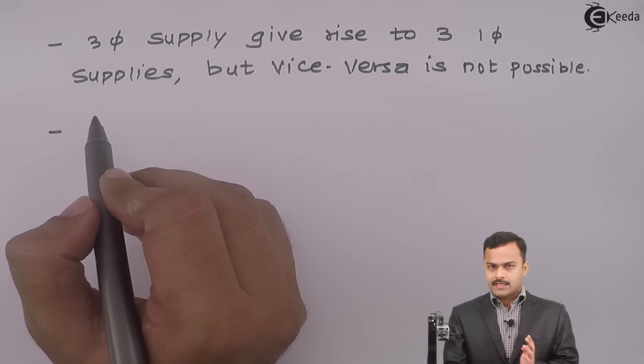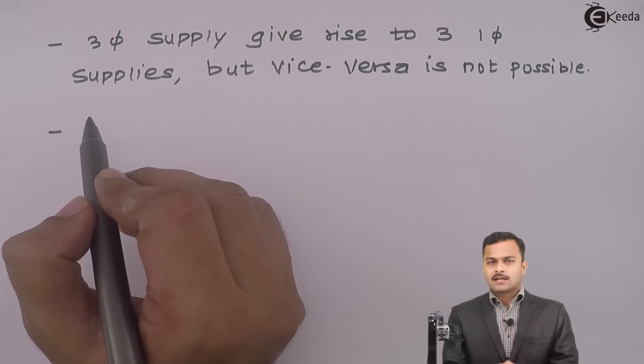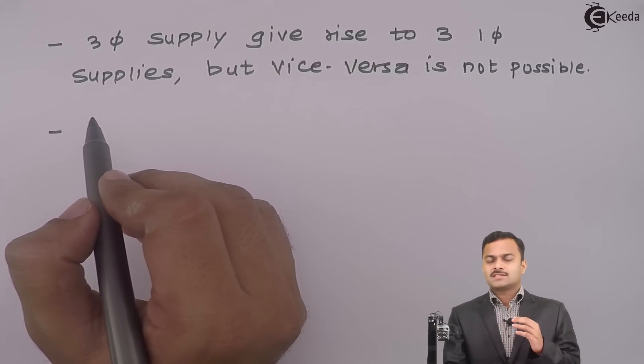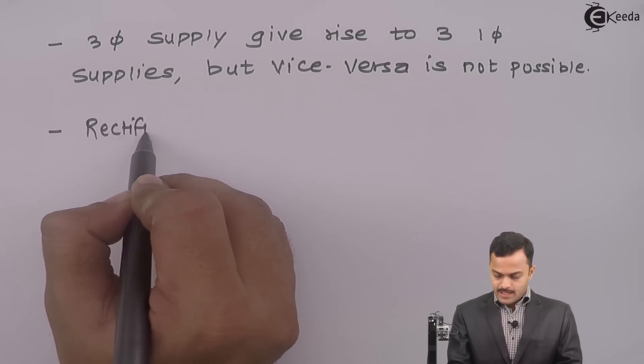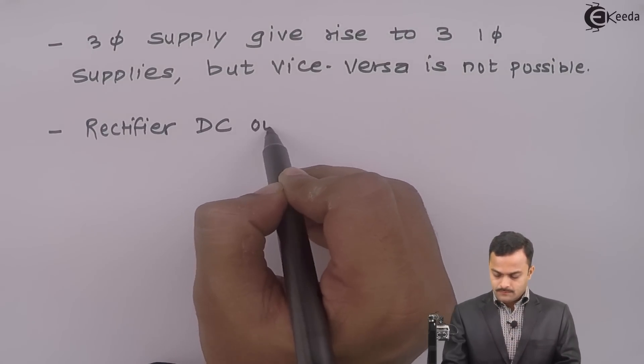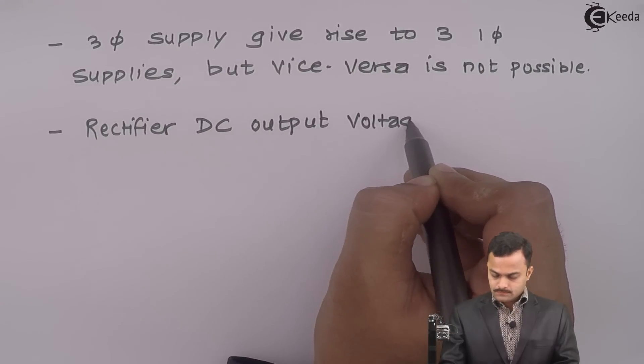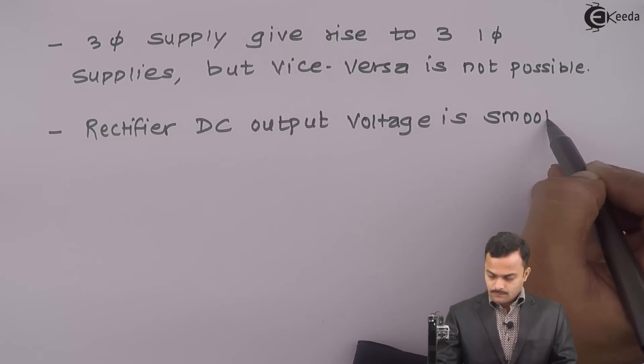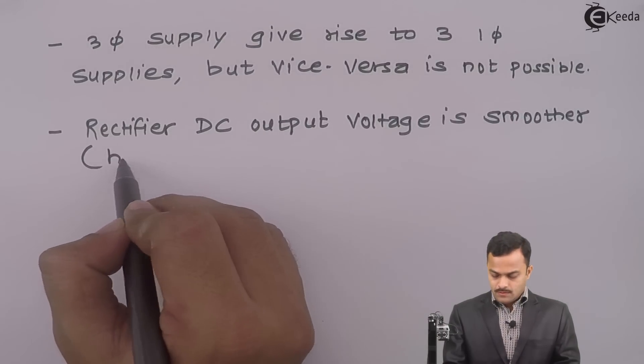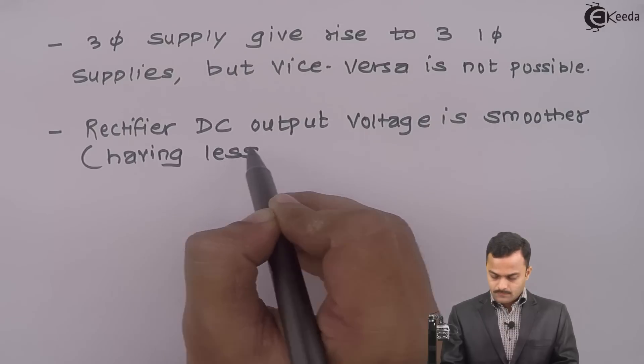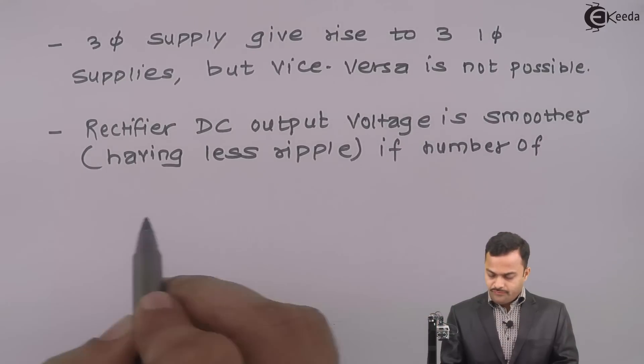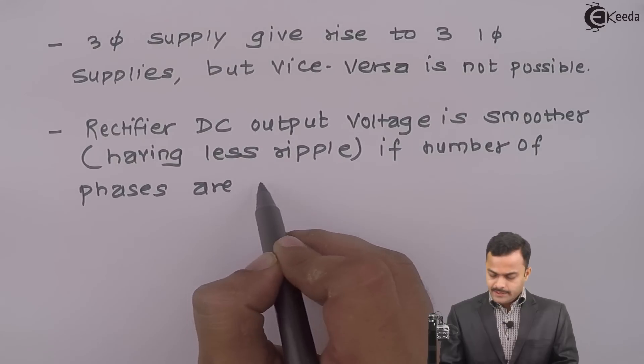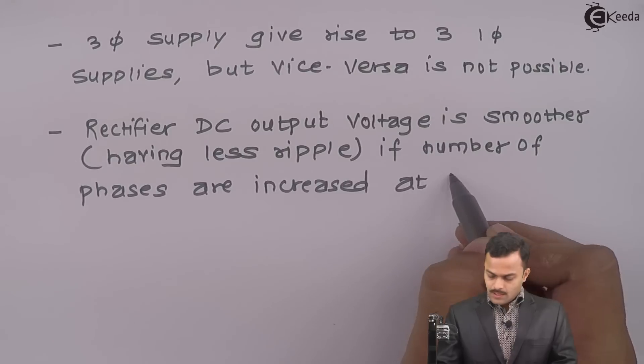Next advantage is, suppose I am converting this three phase supply into DC. The DC I will get is much more smoother than that of a single phase supply DC. What does that mean? Ripple will be very low. So, rectifier DC output voltage is smoother, having less ripple, if number of phases are increased at the supply side.